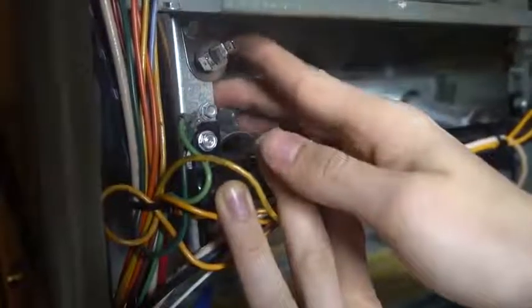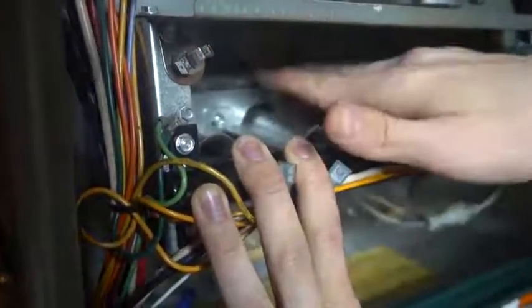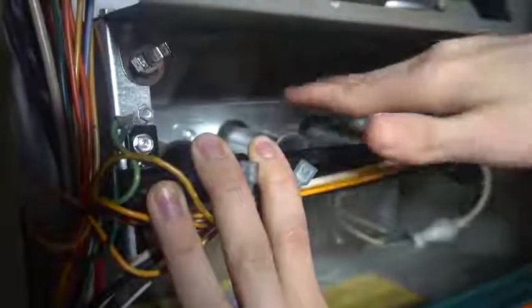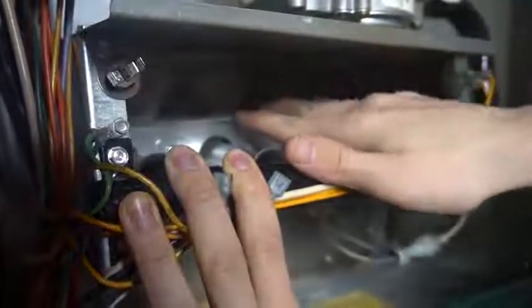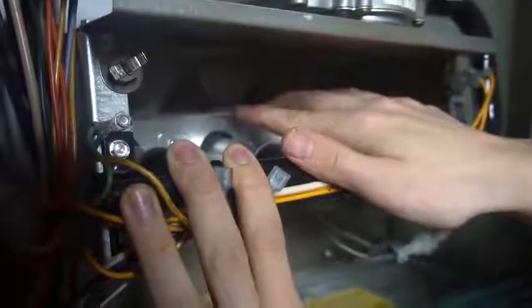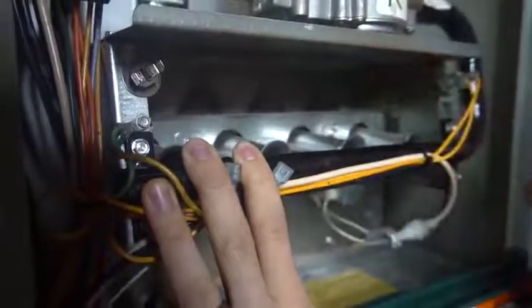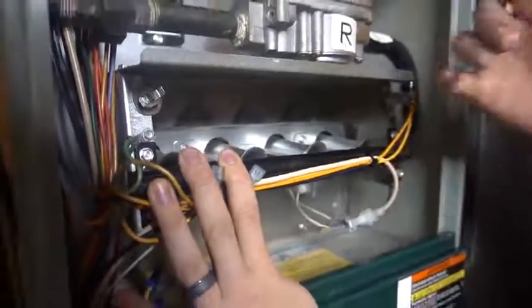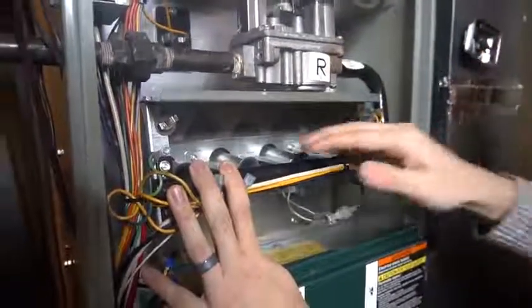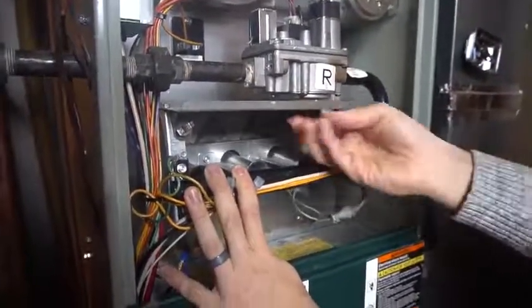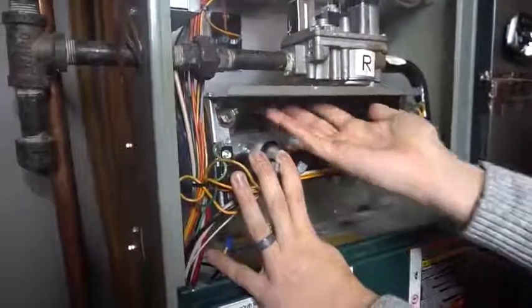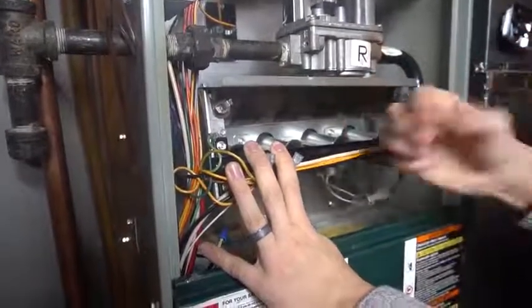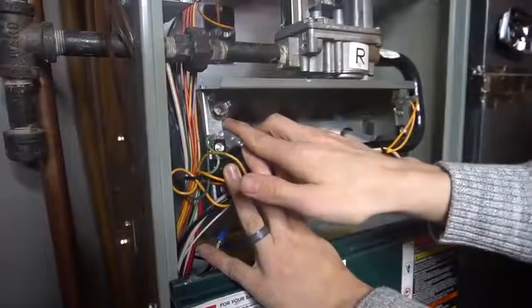So the reason for this thing is the heat or the flames should all be getting sucked into the heat exchanger. If for some reason your heat exchanger is blocked, or for example the chimney cap on your roof collapses or gets iced over, the exhaust fumes that are supposed to be exhausting out the chimney will start to roll backwards. So your flames are going to start to lick the collector box and kind of roll out backwards. That's why these are called flame rollout switches.